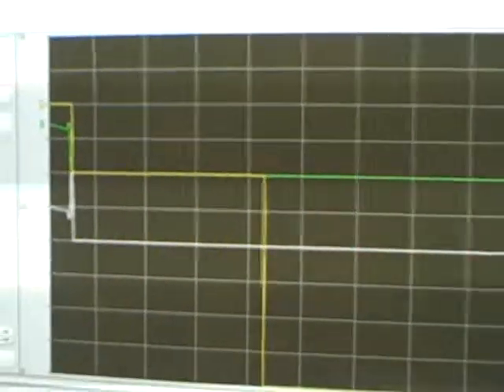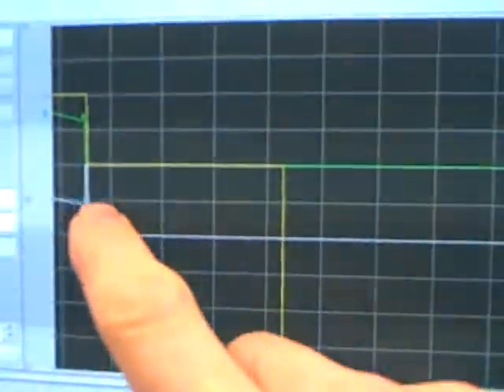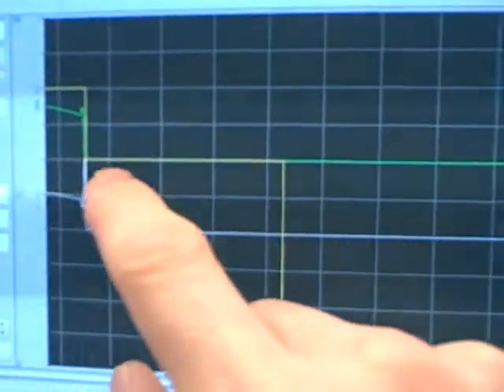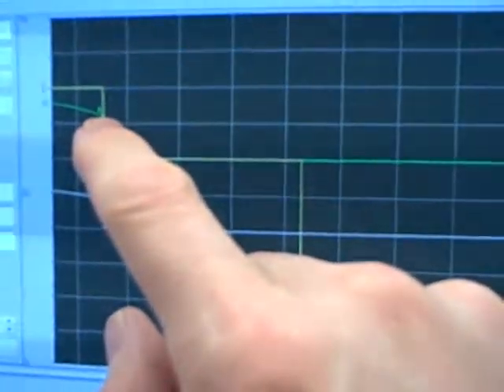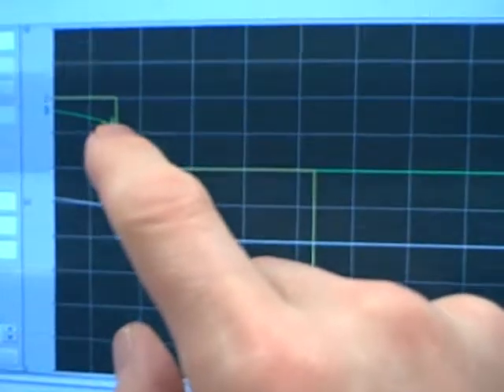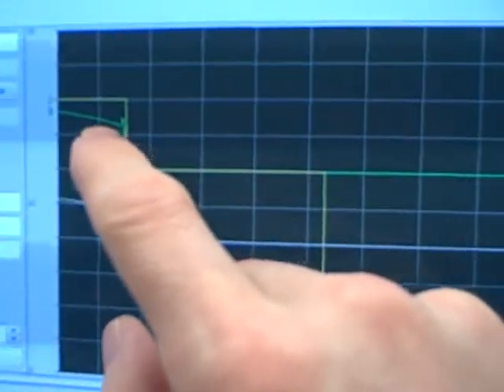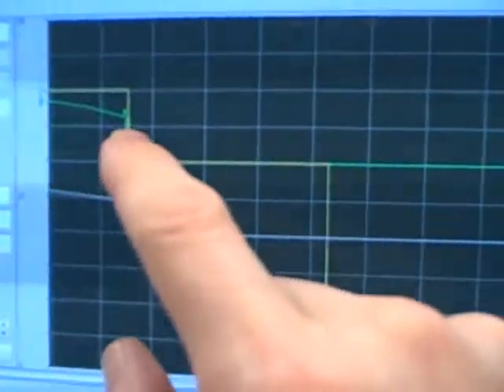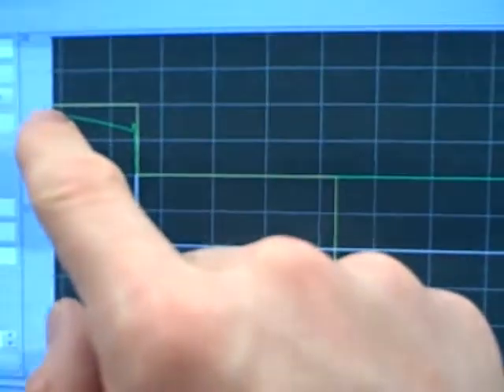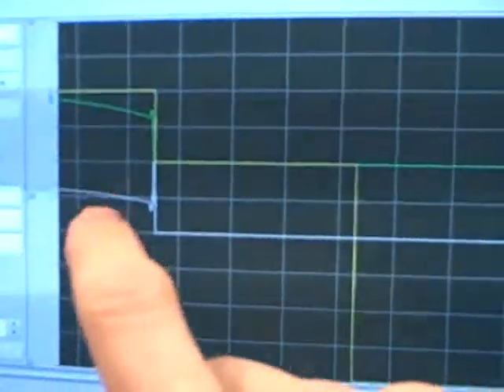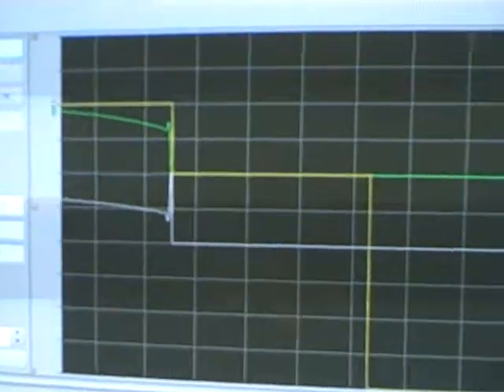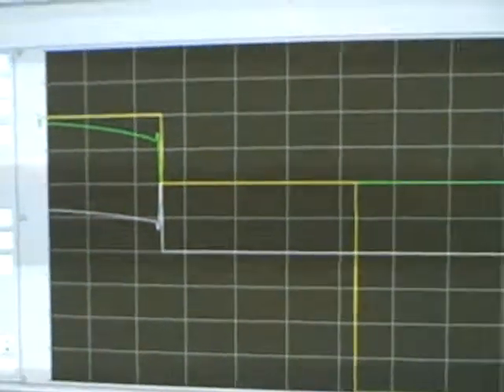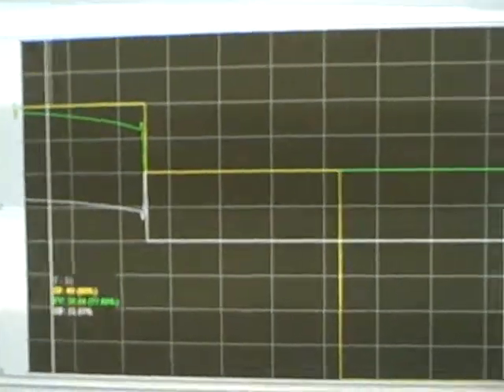Here what we see is the output took an immediate step up. The flow in green took an immediate step up as well. It didn't quite reach set point, and now we're slowly rising to set point. This rise you see right here is due to integral action winding up the valve right here. I want to pause it for a moment and take a look at the response.